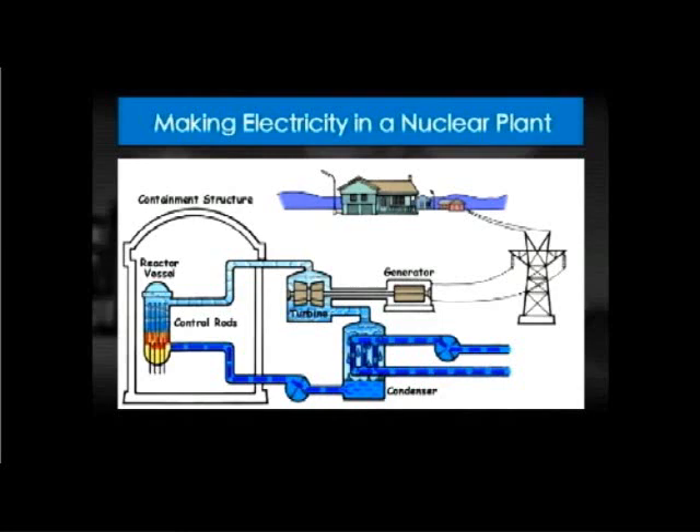There's a second loop of river water that runs adjacent to the radioactive water but doesn't contact it directly — that's in the thing called the condenser. The condenser is probably twice as big as this room. It runs river water through one side of pipes that cools the steam and makes it water again. When you hear about a power plant having a condenser leak, that's river water that leaks into the condenser. The pressures are such that the river water goes into the reactor, not the other way. When Vermont Yankee springs a condenser leak, it's dirty river water going into the nuclear reactor, not radioactive water going out into the river.